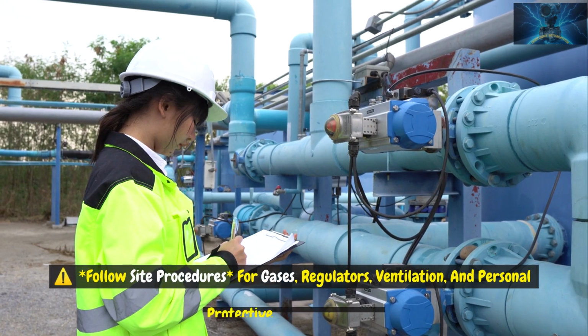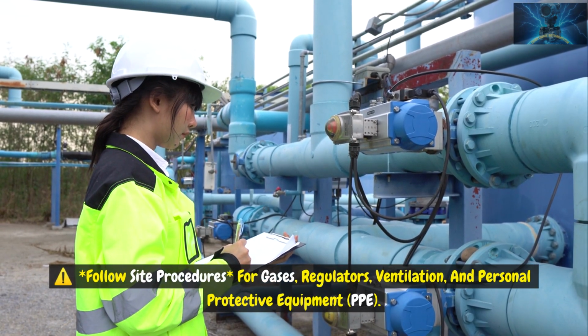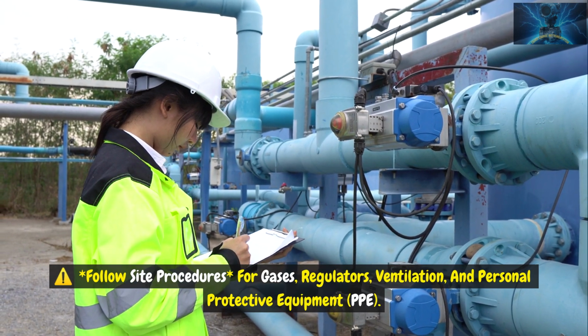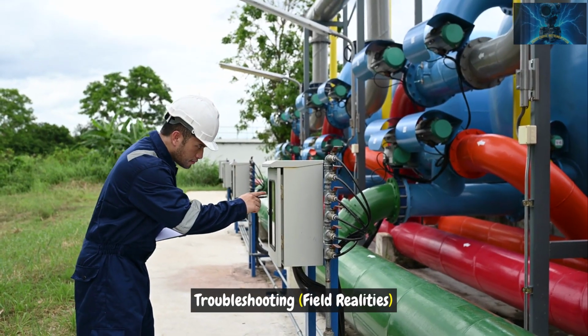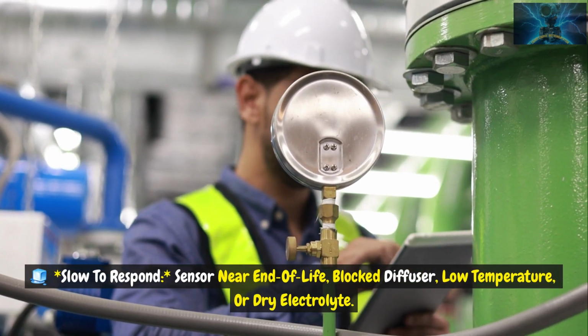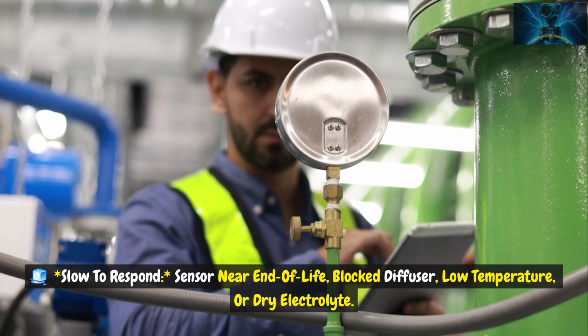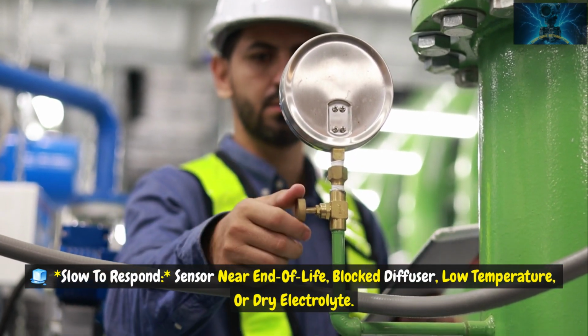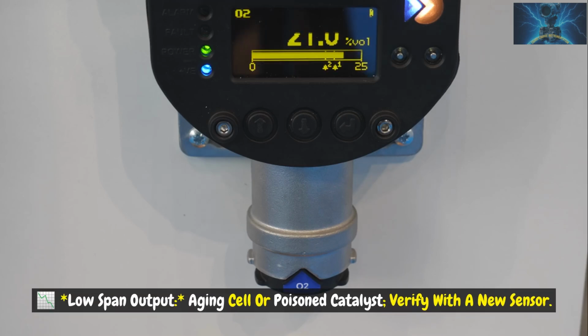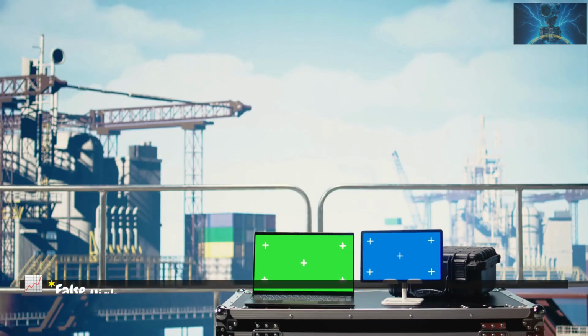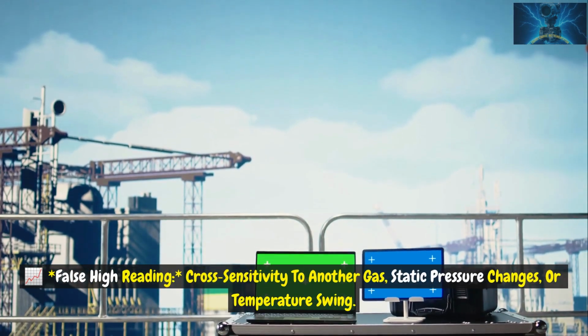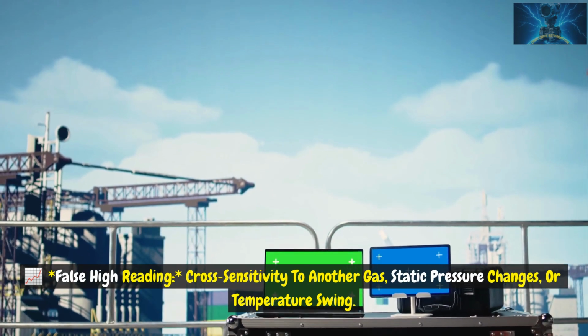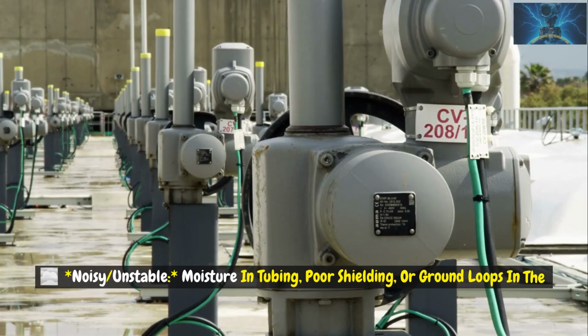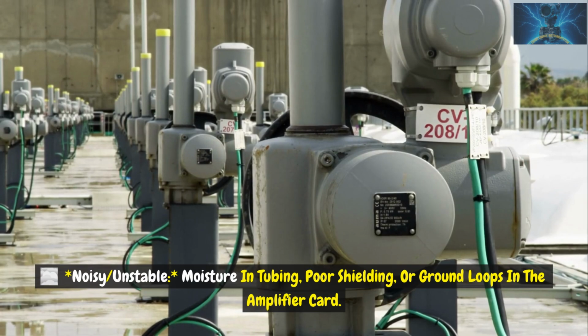Follow site procedures for gases, regulators, ventilation, and personal protective equipment, PPE. Troubleshooting, field realities. Slow to respond: sensor near end of life, blocked diffuser, low temperature, or dry electrolyte. Low span output: aging cell or poisoned catalyst, verify with a new sensor. False high reading: cross sensitivity to another gas, static pressure changes, or temperature swing. Noisy, unstable: moisture in tubing, poor shielding, or ground loops in the amplifier card.